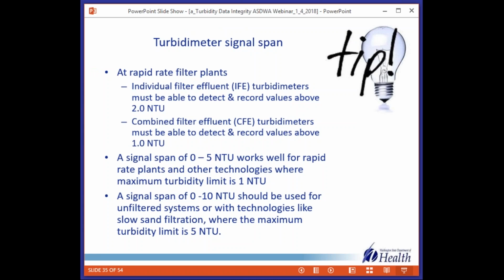At rapid rate filter plants, a reminder that the individual filter effluent must be able to detect and record values above 2.0, and the combined filter effluent must be able to detect and record above 1.0. So we think a signal span of 0 to 5 NTU works well for these rapid rate plants and other technologies where maximum turbidity limit is 1 NTU. A signal span of 0 to 10 could be used or should be used for unfiltered systems, or with technologies like slow sand filtration, where the maximum turbidity limit is 5 NTU.